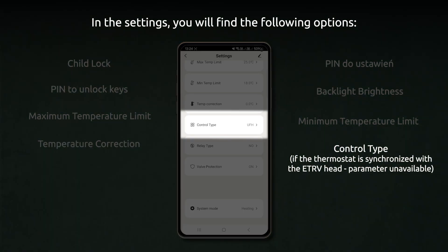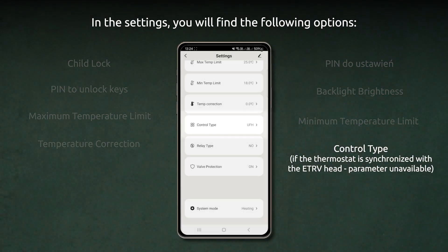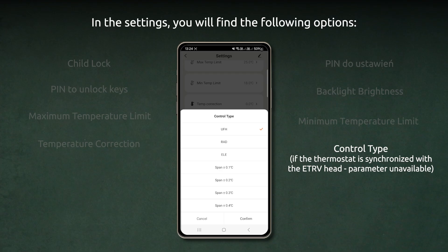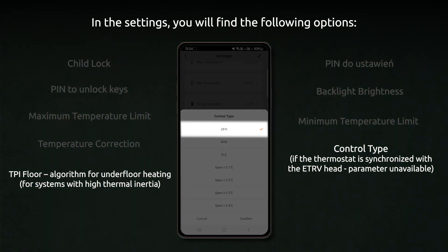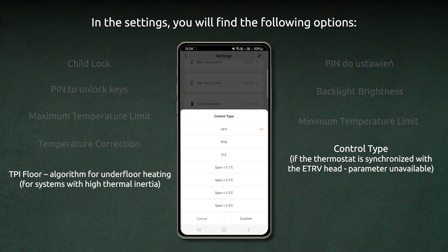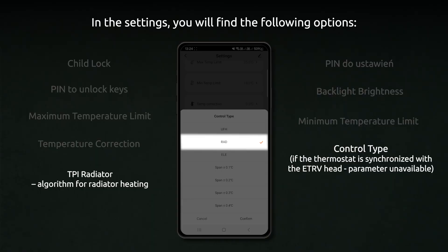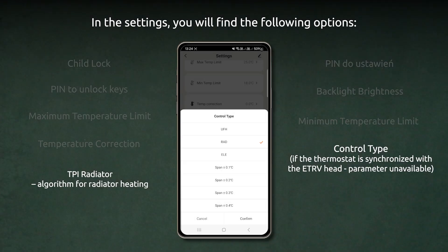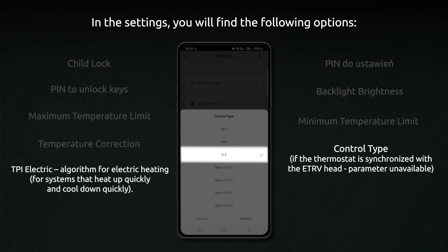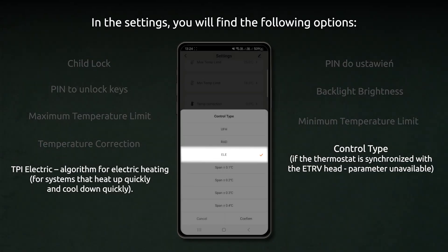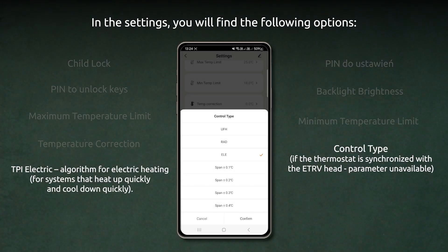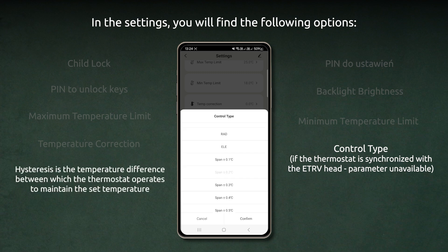Control algorithm. If the thermostat is synchronized with the ETRV head, this parameter is unavailable. TPI Floor algorithm is for underfloor heating for systems with high thermal inertia. TPI Radiator algorithm is for radiator heating. TPI Electric algorithm is for electric heating for systems that heat up quickly and cool down quickly. TPI Hysteresis is the temperature difference between which the thermostat operates to maintain the set temperature.